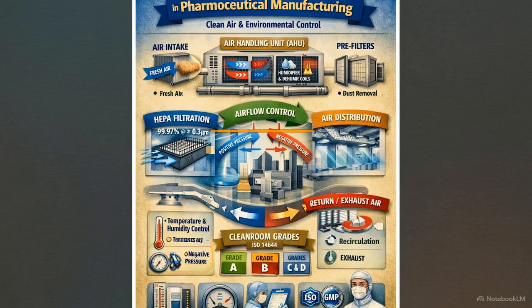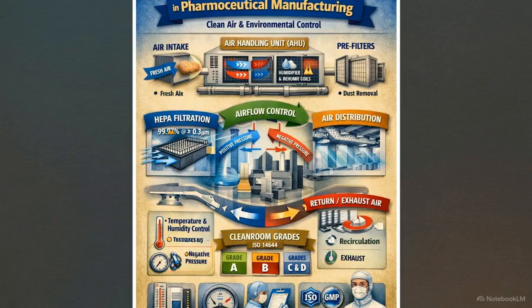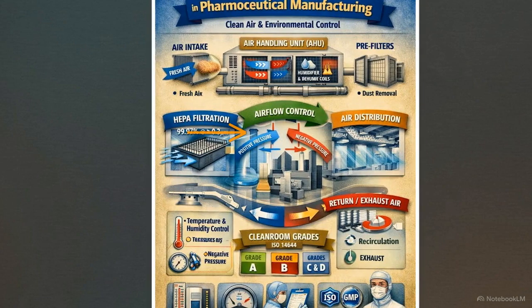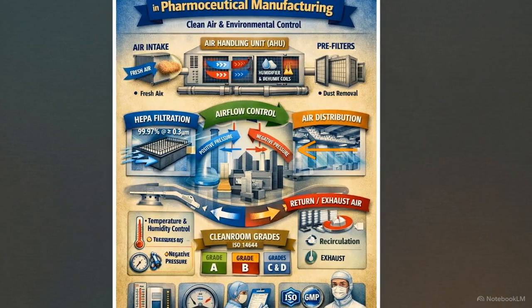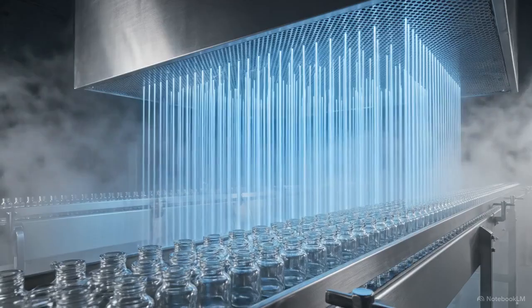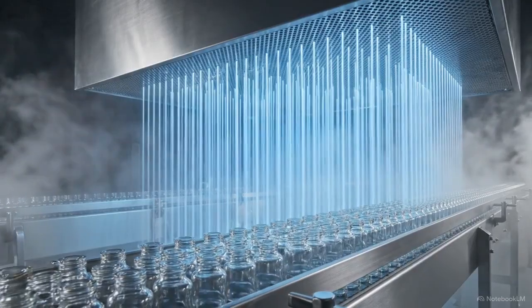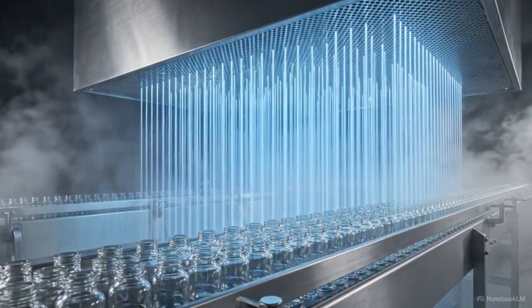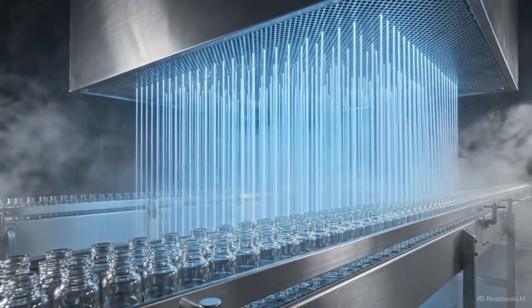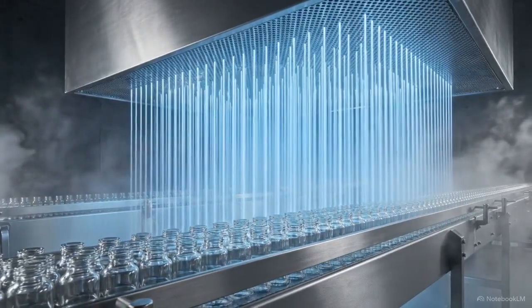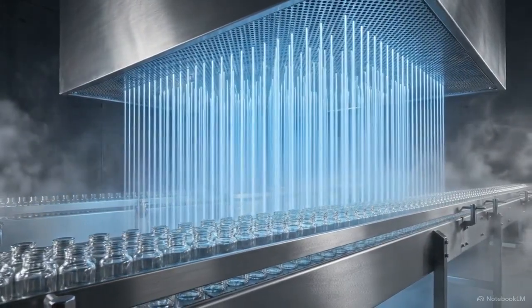This diagram outlines how the system controls airflow and pressure boundaries. Positive pressure in sterile zones pushes potential contaminants outward whenever a door opens. Conversely, areas handling hazardous materials use negative pressure, pulling air inward to ensure dangerous compounds cannot escape. Inside critical sterile zones, the system employs laminar airflow. These unidirectional, parallel streams create a protective curtain over highly sensitive areas, like open drug vials.